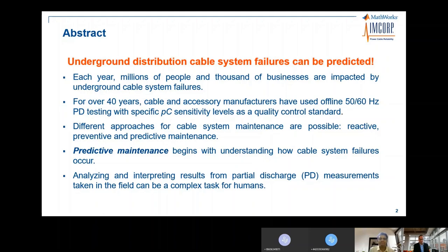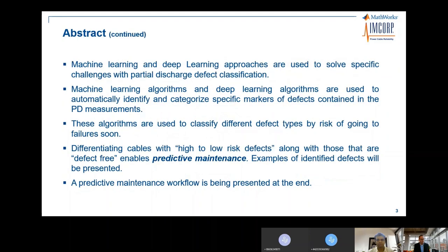Different approaches for cable system maintenance are possible: reactive, preventive, and predictive. Predictive maintenance begins with understanding how cable system failures occur. Machine learning and deep learning approaches are used to automatically identify and categorize specific markers of defects in partial discharge measurements, classifying different defect types by risk of going to failure soon.